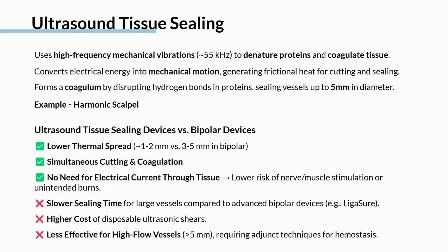A very well-known example of this technology is the harmonic scalpel. The key advantages include lower thermal spread. The ultrasonic devices in general have a thermal spread of just 1 to 2 millimeters versus 3 to 5 millimeters in the bipolar devices. They can also offer simultaneous cutting and coagulation ability, and this improves efficiency during dissection, and there's no electric current that travels through tissue.